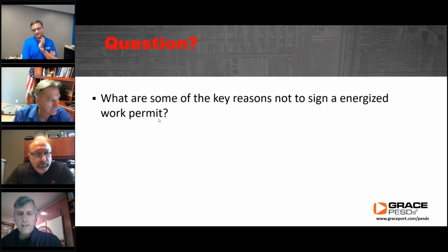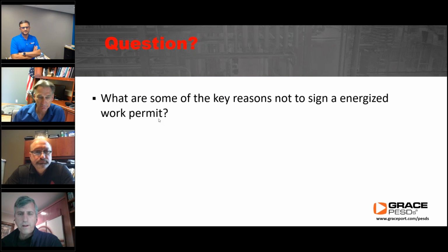Let's talk about when you might need an energized permit. One would be if you're purposefully making rubber glove contact with energized parts, which shouldn't happen very often. If you're doing work beyond diagnostic work, that's also considered permit work. In other words, the regulations acknowledge you have to have an energized reference point to do troubleshooting. So while in troubleshooting mode, they allow you to have a reference point where you'd be taking volt readings, for example, to figure out if you have a blown fuse or whatever.